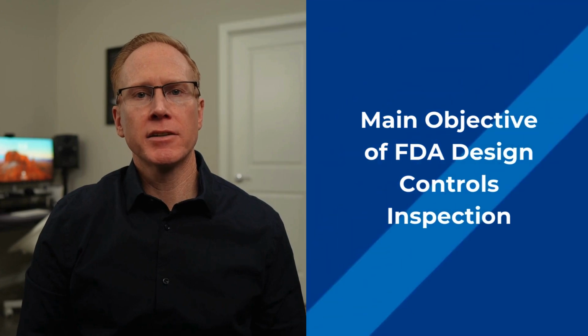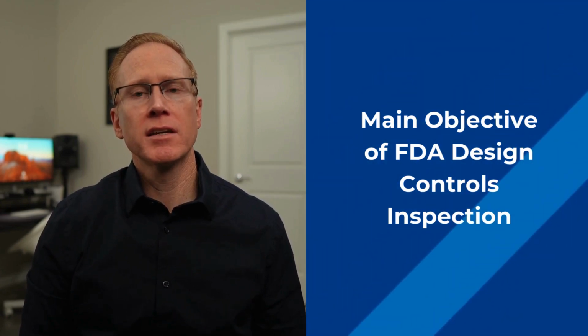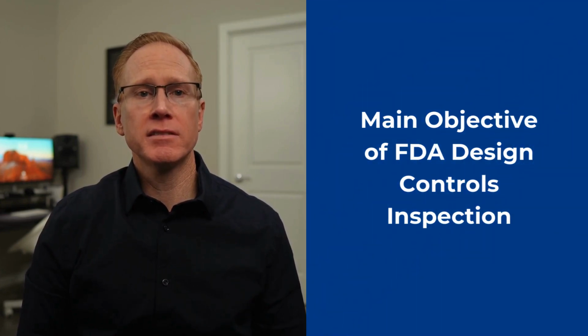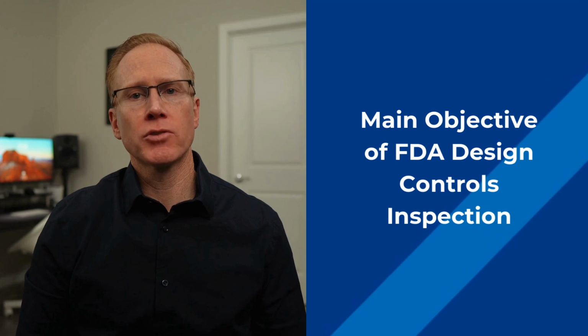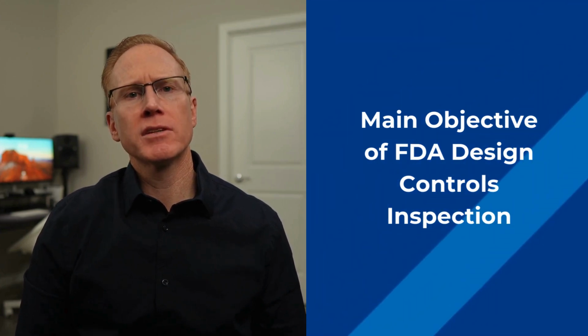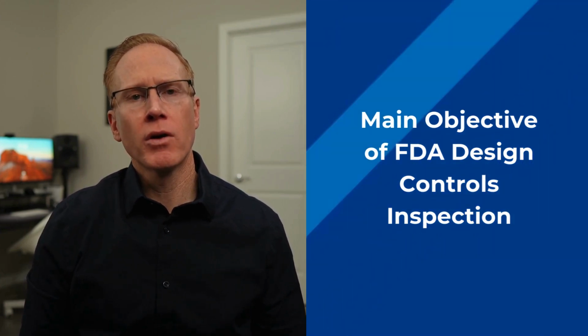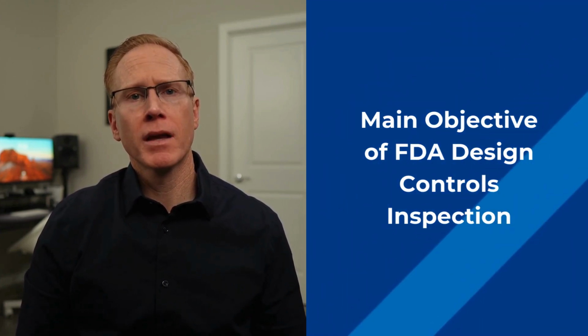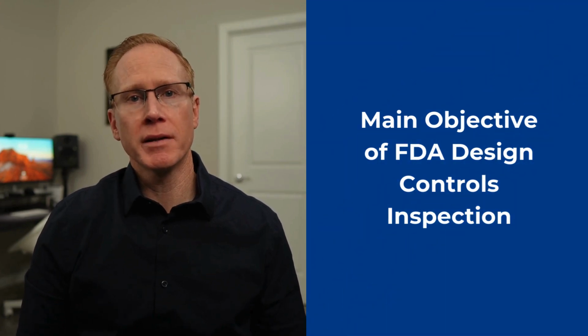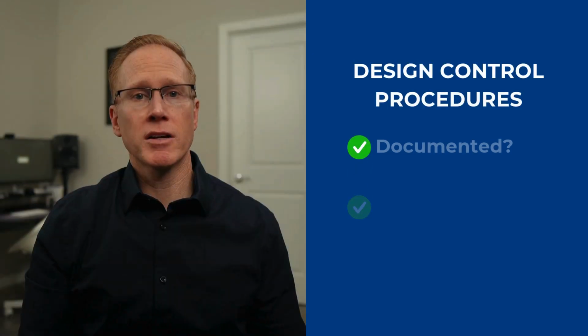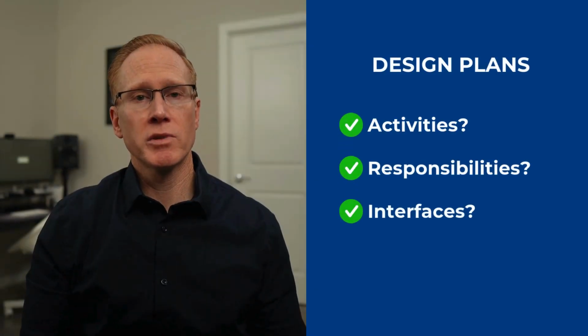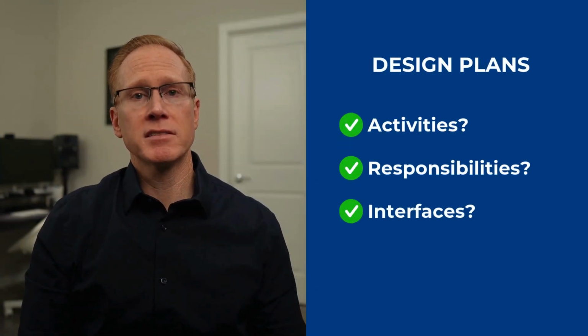Let's get started. During an inspection, FDA investigators focus on whether your design process ensures the device meets user needs, intended use, and regulatory requirements. They'll also assess whether your design history file, or DHF, is compliant. Here are the main objectives they'll evaluate. Design control procedures. Are they documented and implemented? Design plans. Do they outline activities, responsibilities, and interfaces clearly?